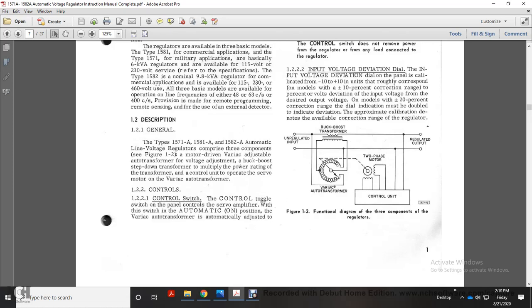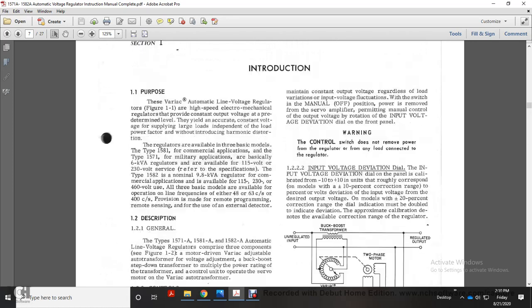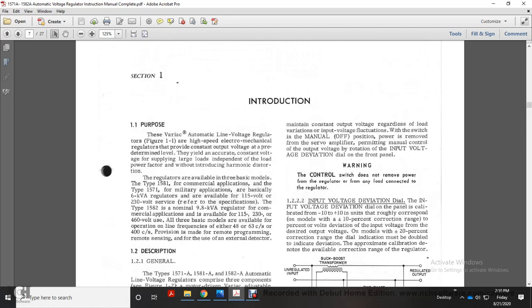1-2-1, controls. Control switch. The control toggle switch on the panel controls the servo amplifier. With the switch in the automatic on position, the Variac autotransformer automatically adjusts to maintain constant output voltage regardless of the load variation or input voltage fluctuation. With the switch in the manual off position, power is removed from the servo amplifier, permitting manual control of the output voltage by rotating the input voltage deviation dial on the front of the panel. Warning: the control switch does not remove the power from the regulator or from any load connected to the regulator.